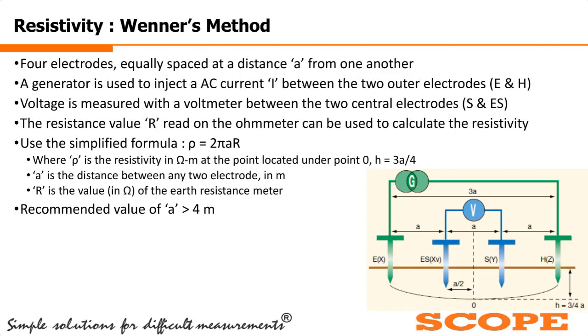So we always have to calculate this earth resistivity, because the instrument will only measure the resistance value. So with the help of rho equals 2 pi A R, a simplified formula, we get the resistivity. The recommended distance between any two spikes is greater than 4 meters, and generally the depth of the earth electrodes is h equals 3a divided by 4.